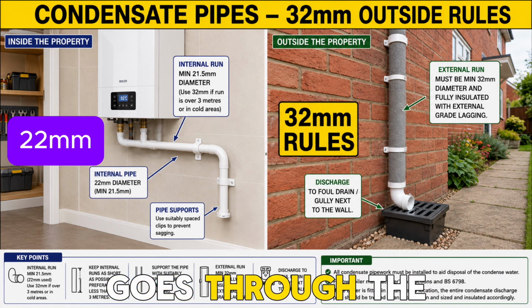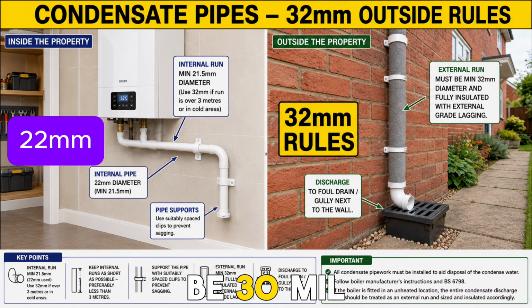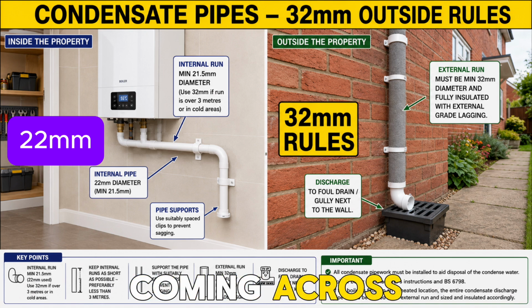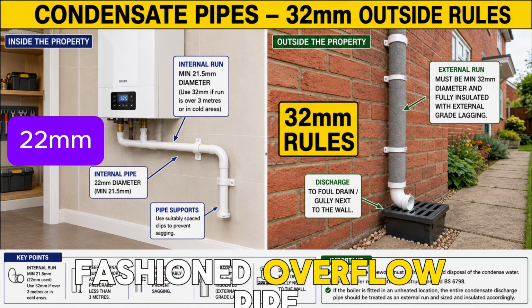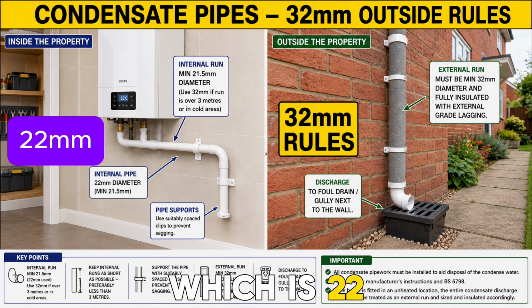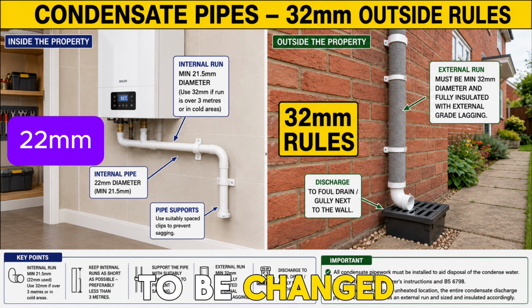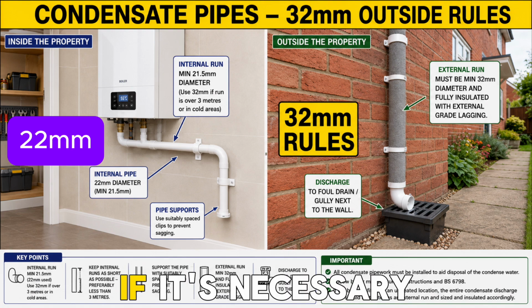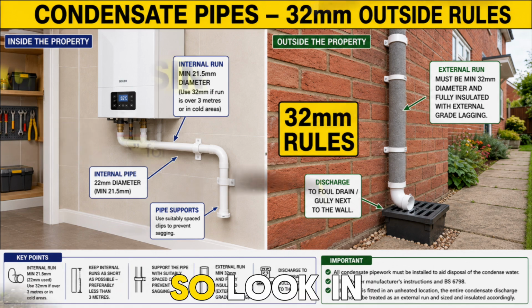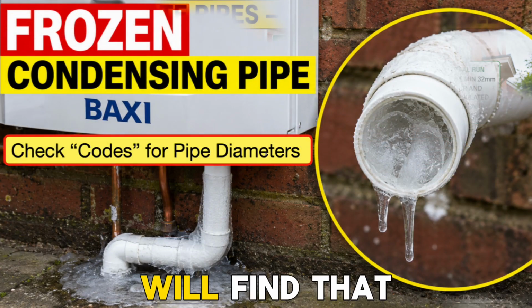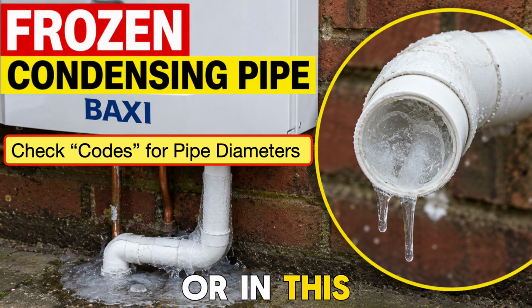Now, if it goes through the wall, it's going to be 32 mil. So if you're coming across still the old-fashioned overflow pipe, which is 22 mil, that has to be changed, and it has to be lagged if it's necessary. So look in the manual for guidance, or phone that manufacturer, or in this case it can be Baxi, asking for guidance. So that's important.